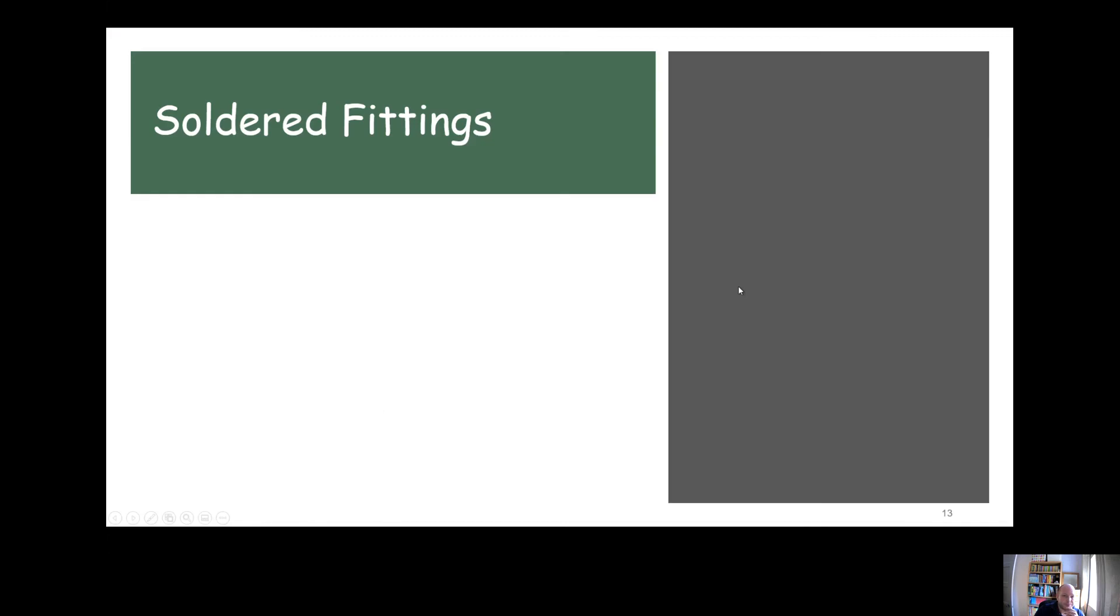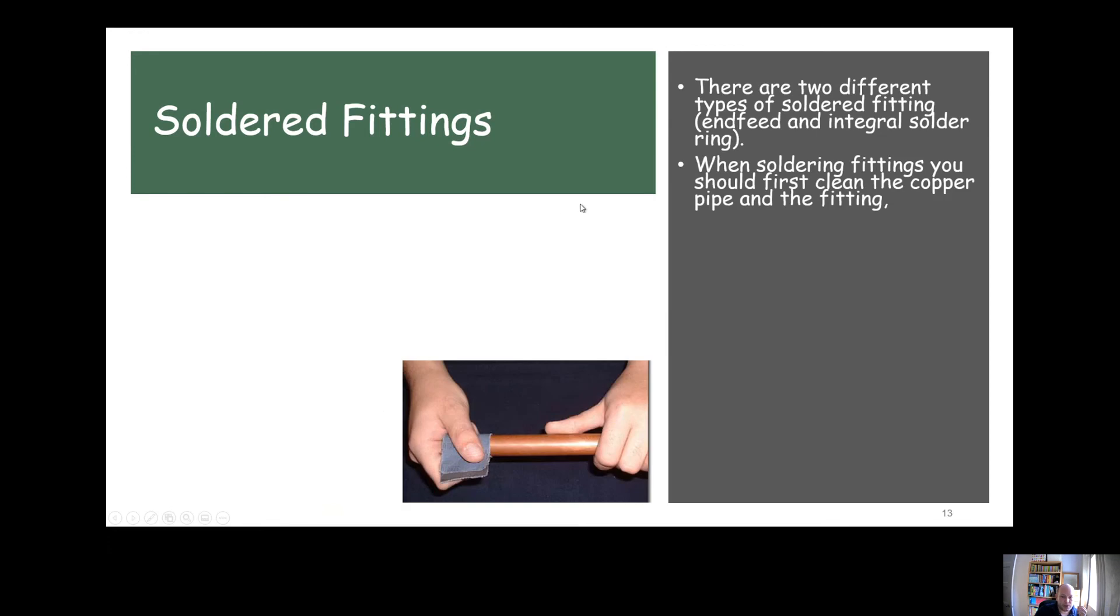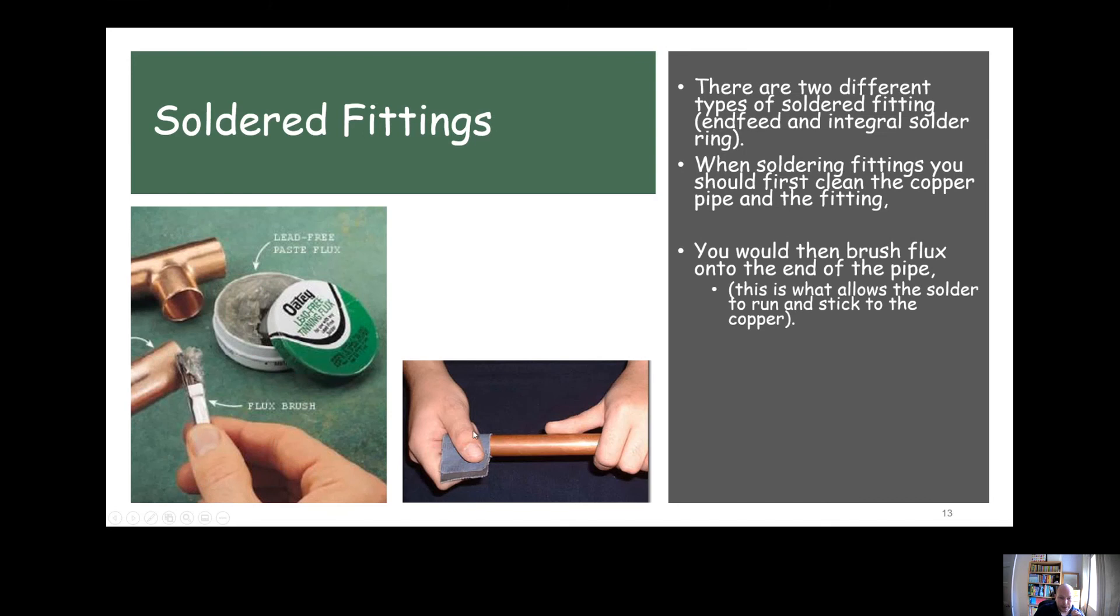For soldered fittings, there's two types: end feed fittings and integral solder ring fittings. The jointing process is almost exactly the same for both. When you solder fittings, you firstly clean up the pipe with an abrasive cloth or piece of steel wool. You should also clean the inside of the fitting, and then put some flux onto the end of the pipe only. Don't put it into the fitting, because if you push the flux inside the fitting, you end up with a buildup of flux inside. Just put the flux on the clean end of the pipe and then push that into the clean fitting.